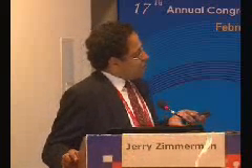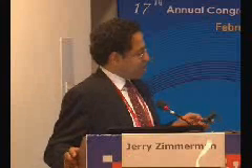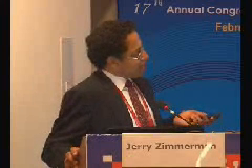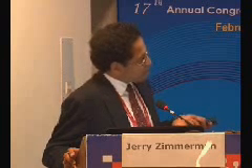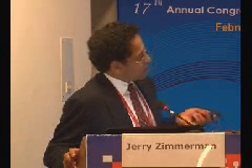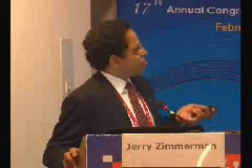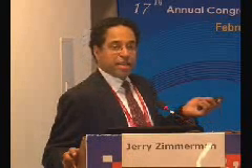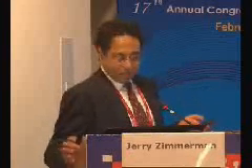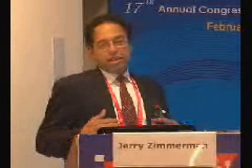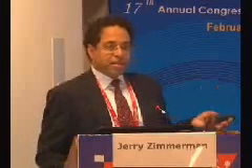This is the system we use at our hospital, and I saw yesterday that they have a display at booth 72 and 73 if you're interested in looking at it. This is your Foley catheter connecting to this system, which essentially provides a fluid column which connects to this pressure transducer and a monitor cable which displays on your monitor, much in the way we display arterial pressure or CVP. And just like with arterial pressure or CVP, there has to be a continuous column of fluid. So if there's bubbles or debris in there, that's not going to work.